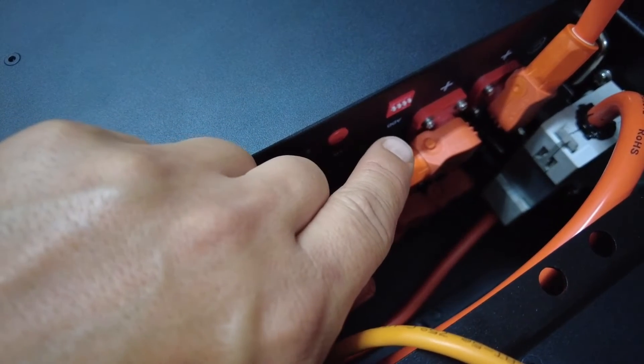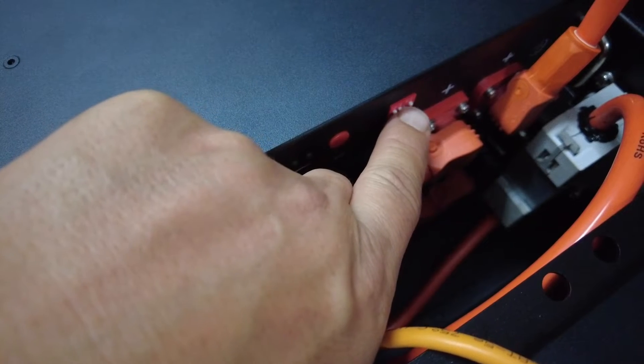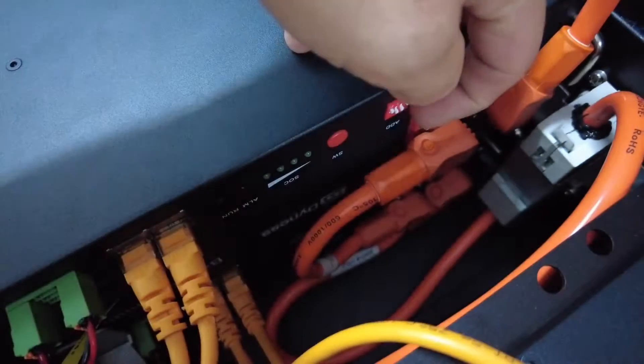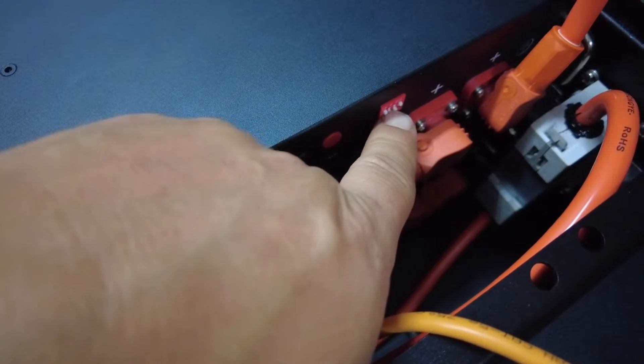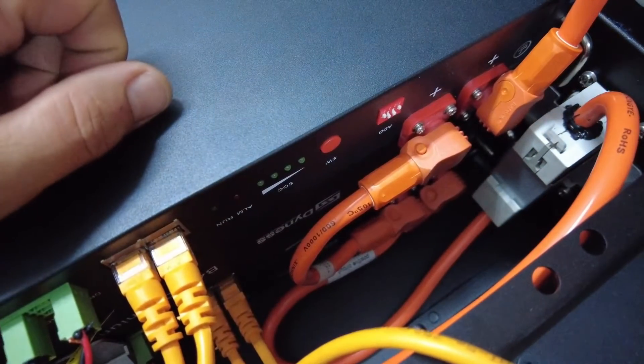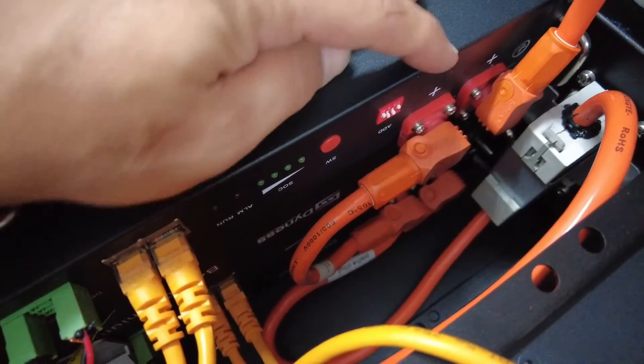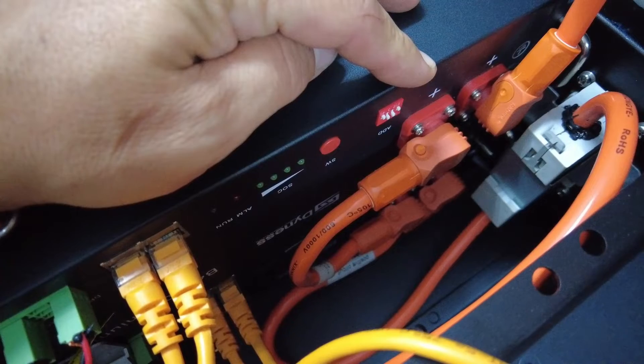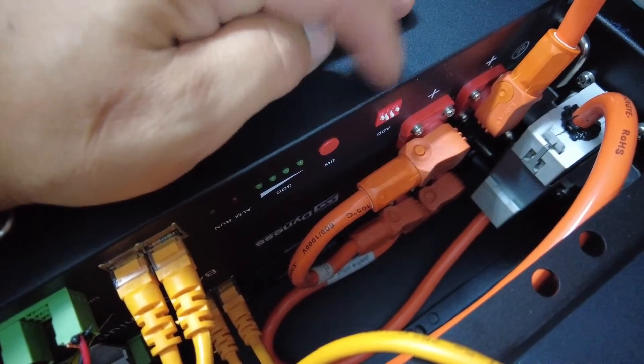In this case, being a Growatt SPF 5000 ES inverter, we need to set the two middle dips in the on position. We refer to this as 0110, or off, on, on, off.